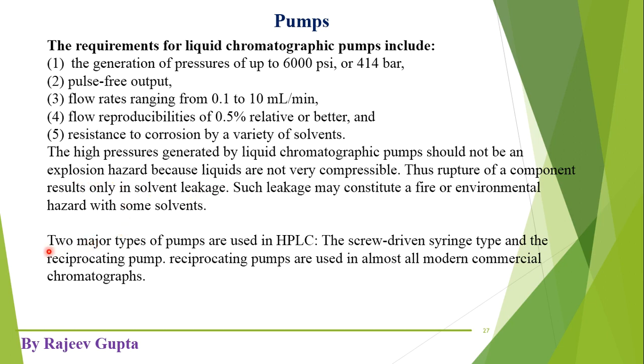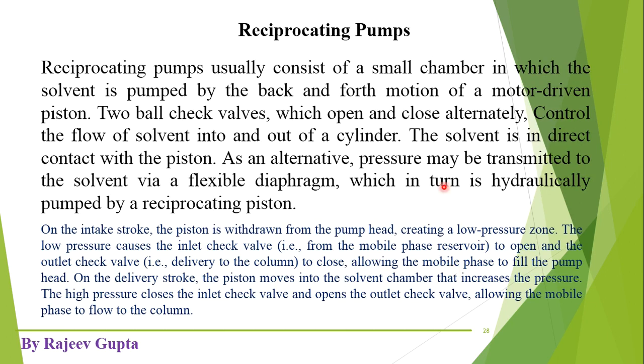Now the types of pumps are shown here. There are two major types of pumps used in HPLC that we will study. Actually three types exist, but one older type is not currently used in modern HPLC instruments. The two types highly used in modern HPLC instruments are: the screw-driven syringe type pump, and the reciprocating pump — with the reciprocating pump being the most widely used.